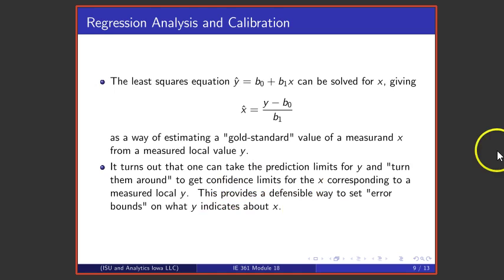You can take the least squares line that is of the form y hat is coefficient b0 plus coefficient b1x and solve for x. And that gives a way to take a y and convert it to an estimated or guessed at gold standard value, true value x. It also turns out to be the case that the prediction limits for y can be turned around to get confidence limits for the x corresponding to a measured value y. And that provides a good way to set error bounds on what a measurement y tells one about the measurand x.